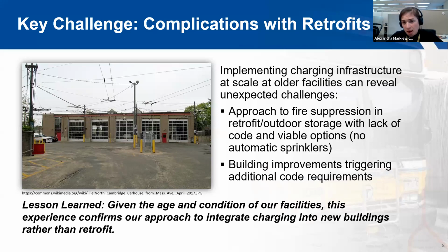But on the other hand, outdoor storage doesn't allow you to install automatic sprinklers like you could indoors. We're finding you really would need to rely on a dry type option, like a dry deluge system, where you'd have open sprinkler heads supplied from water the fire department brings when they arrive and hook into it, which means you have a delta of time between when a fire might begin and have time to spread, and when the fire department arrives and can make use of this type of system.